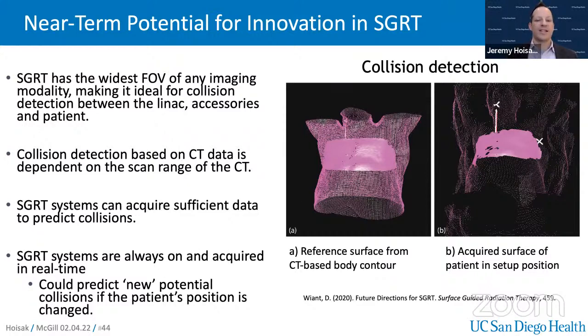Collision detection done prospectively using the CT data set is limited to the scan range of the data set that is used to generate that CT body contour. However, SGRT has a very large field of view. In fact, it has the largest field of view of any imaging modality used in radiation therapy right now. So you can image not just the patient, but any accessories, arm position, the couch, other objects. So this could be something that's always on and alerts therapists that they are about to move the gantry into perhaps the patient. And this does happen, particularly if therapists take their eyes off the patient because of some other distraction.